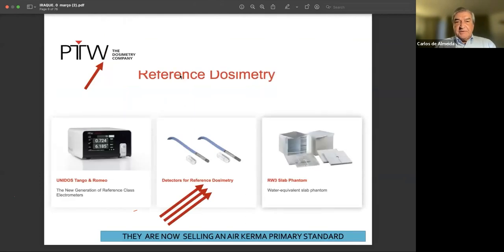PTW is a German company that you also probably know. They used to use the words absolute dosimetry, but I once talked to the company's head about this, and somehow he was convinced that he should not use absolute dosimetry. Now he's using reference dosimetry. In just one case, they are now selling a primary standard for air kerma for radiation protection. So for that particular instrument, they can call it a primary standard.